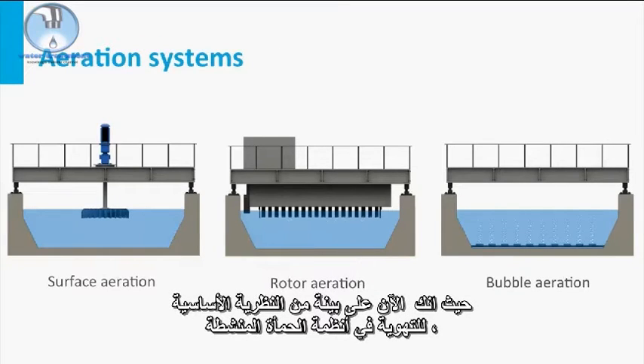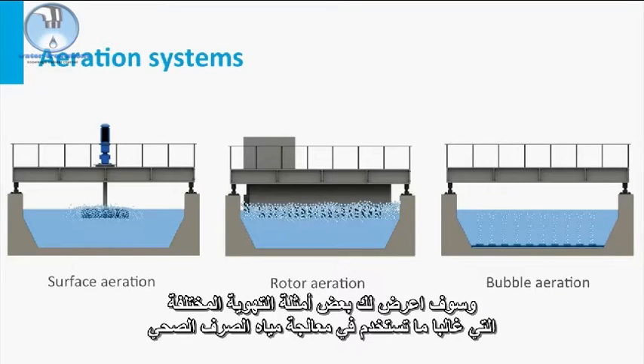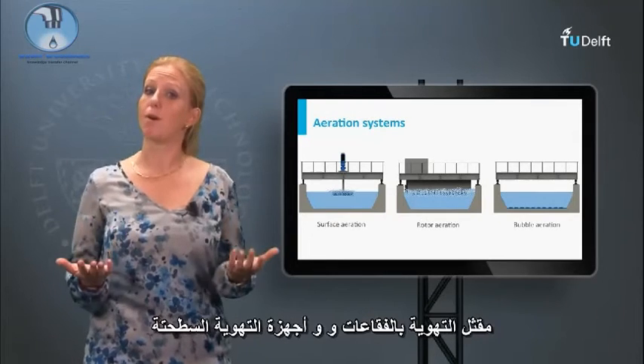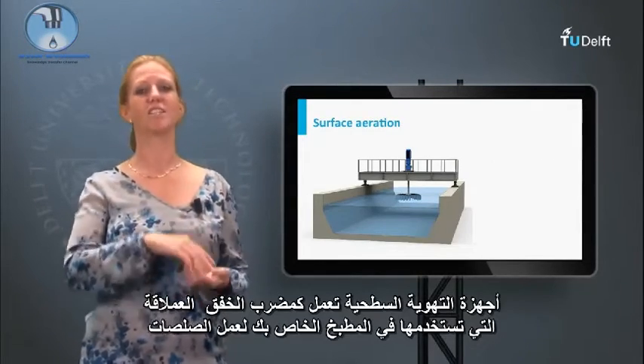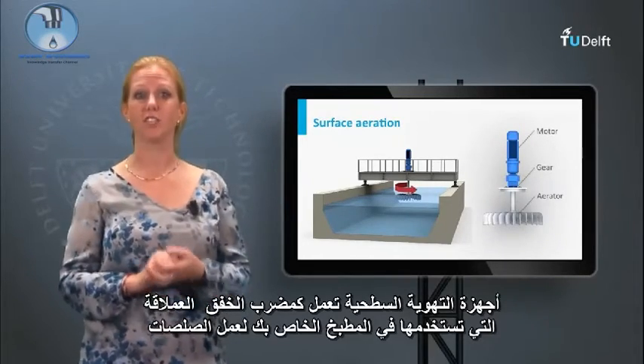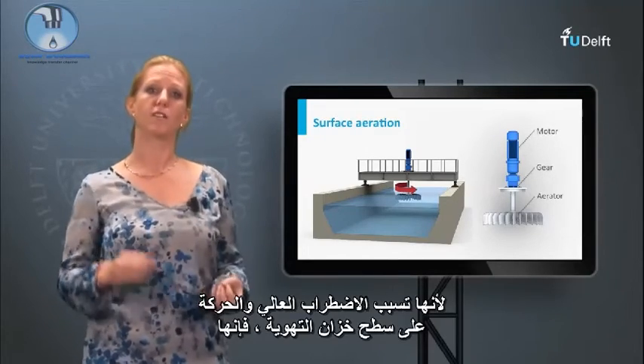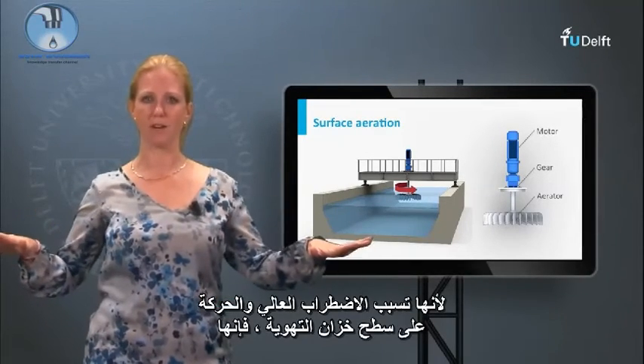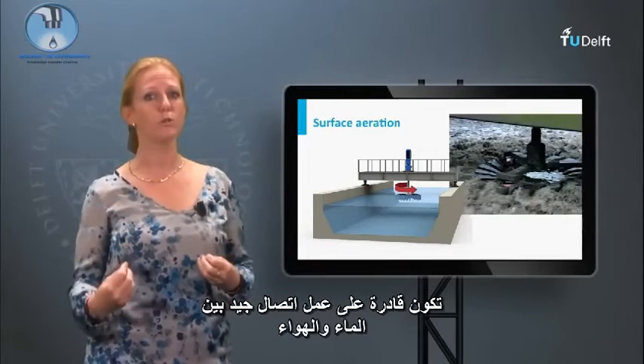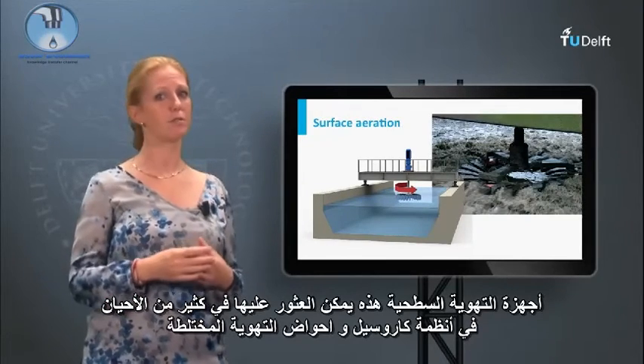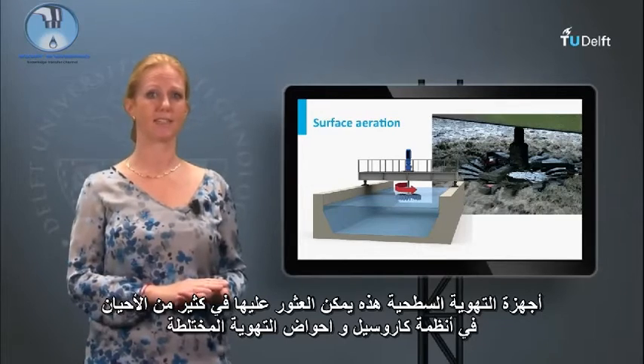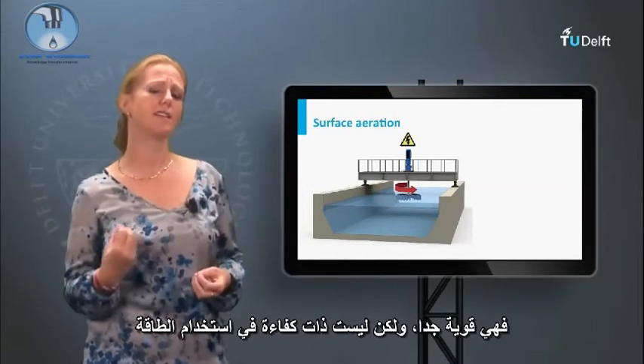Now aware of the basic theory on aeration of activated sludge systems, we will look at examples of different aerators often used in sewage treatment: bubble aeration and surface aerators. Surface aerators function as giant whisks, causing high turbulence and motion at the surface of the aeration tank, generating good contact between water and air. These surface aerators can often be found in carousel systems and mixed aeration tanks. They are very robust, but not that energy efficient.